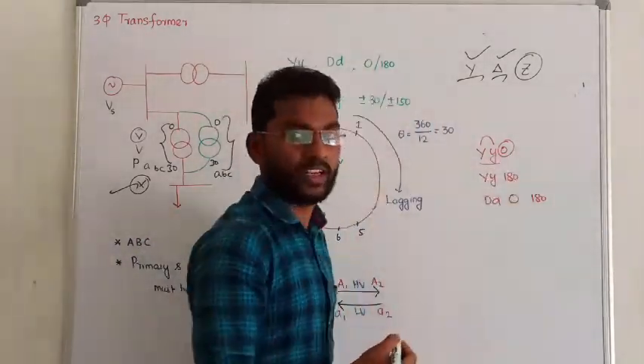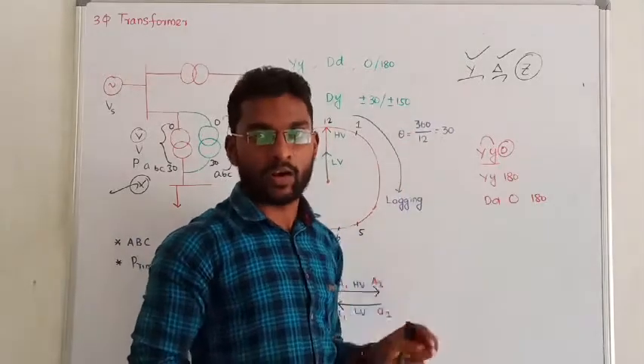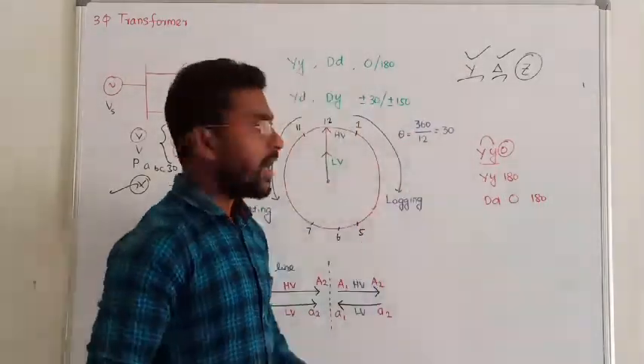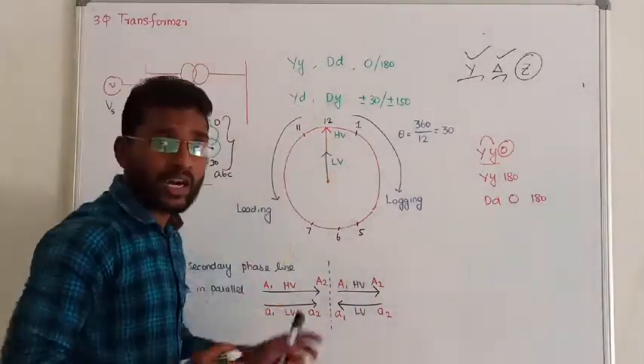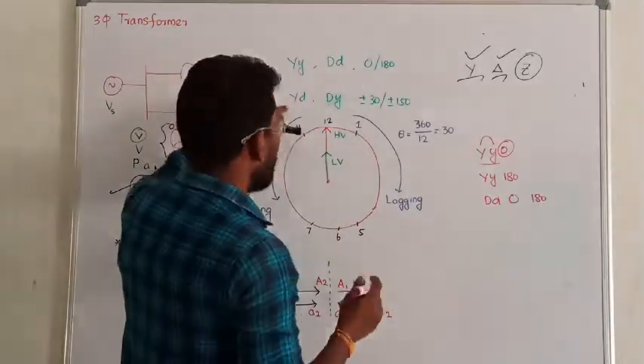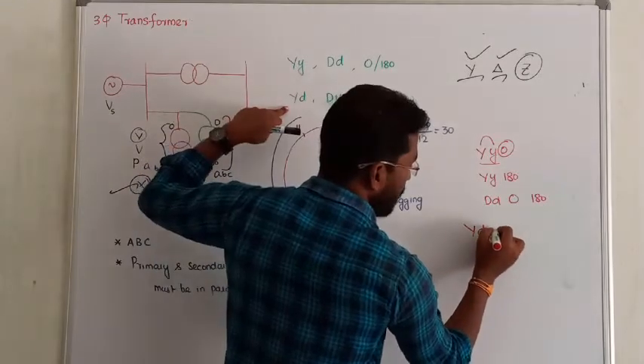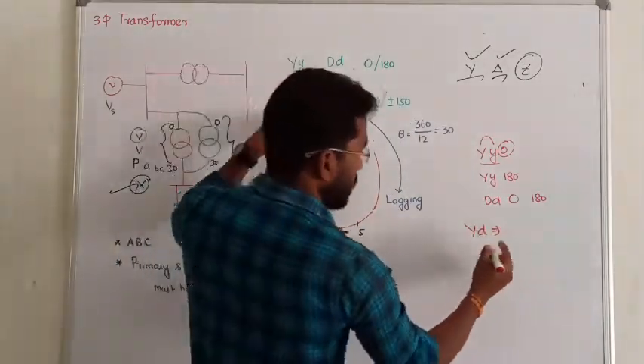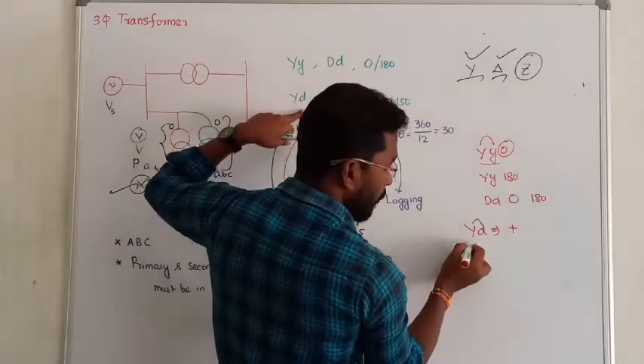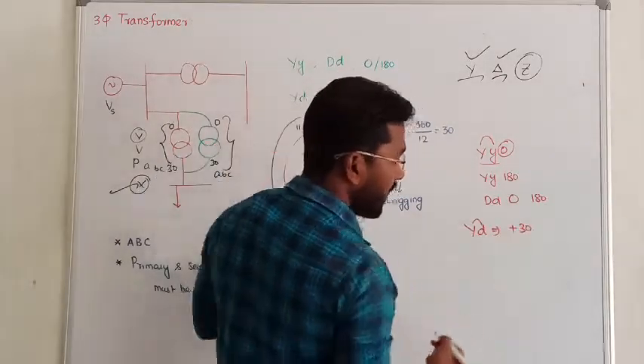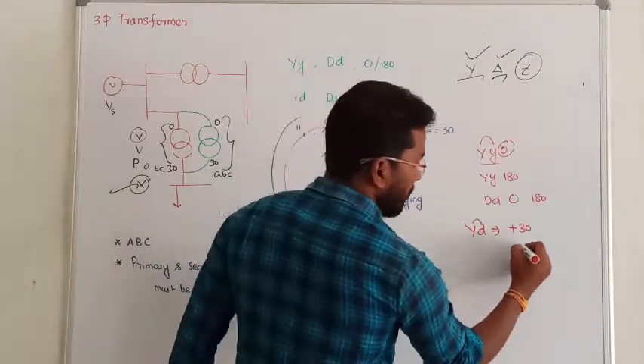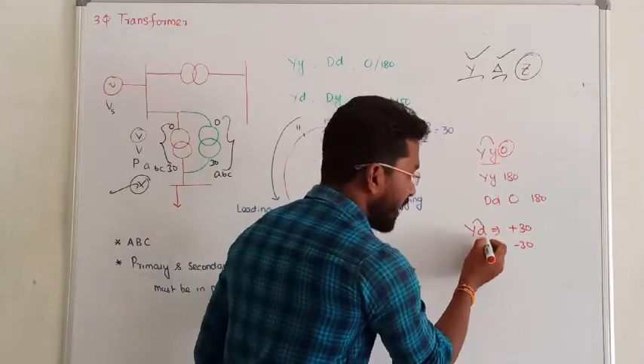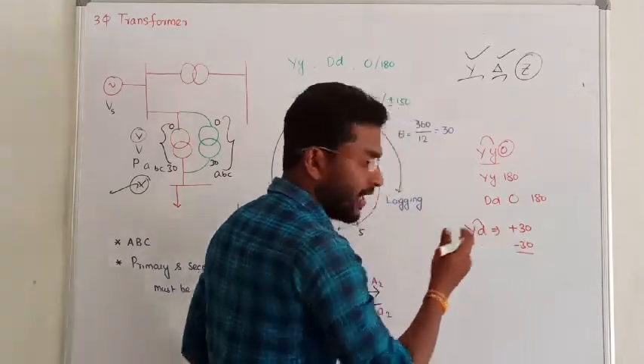In case of the same kind of windings — like star-star or delta-delta — only two phase differences are possible: zero and 180. Now, suppose you choose star and delta — there are also two combinations. For star-delta, primary and secondary would have a plus 30 degree shift, and another option is minus 30 degree, which means secondary is lagging primary.